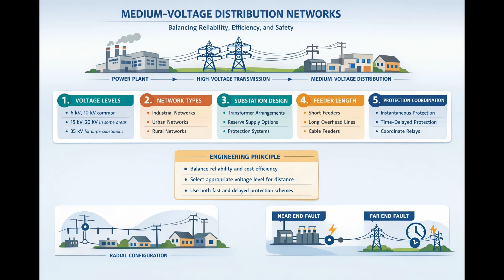In urban cable networks, higher short circuit levels allow broader instantaneous zones. In industrial systems, dual supply and higher fault currents require careful coordination between both ends of the feeder. Medium voltage network design always connects three aspects: topology, voltage level, and protection coordination. Your goal as an engineer is to ensure reliability at minimum cost while maintaining safety and selectivity. Every feeder length, every voltage choice, and every relay setting influences system performance. This is why medium voltage distribution engineering requires both technical precision and economical reasoning.